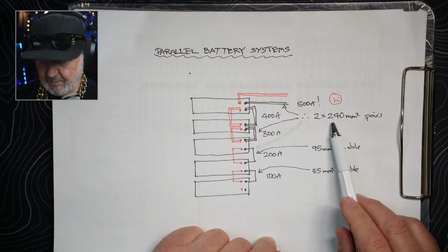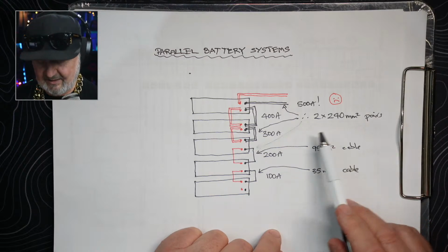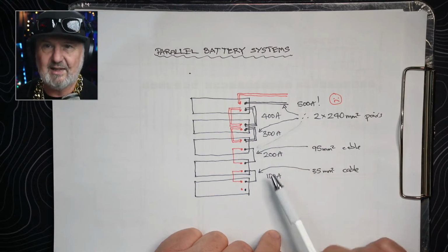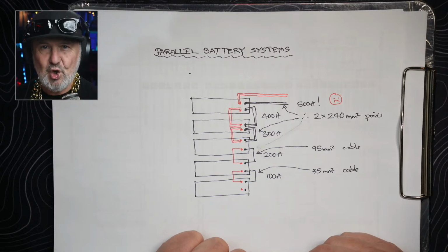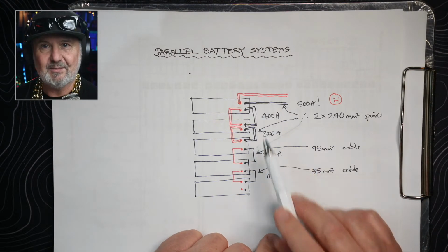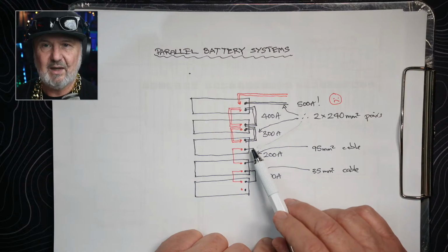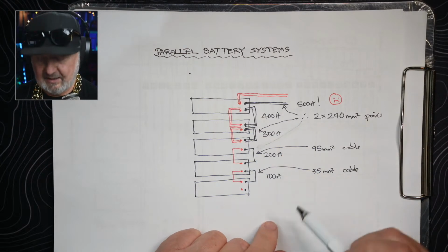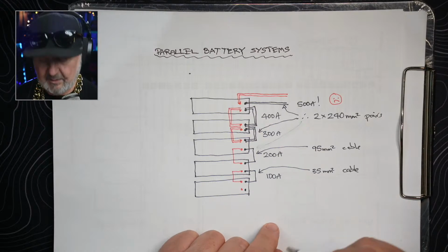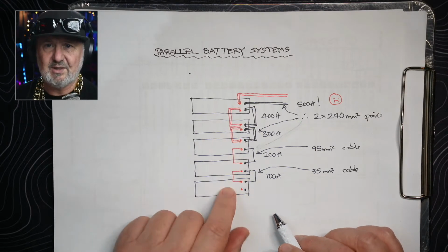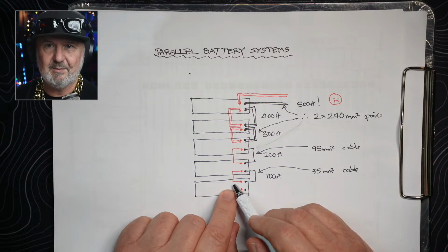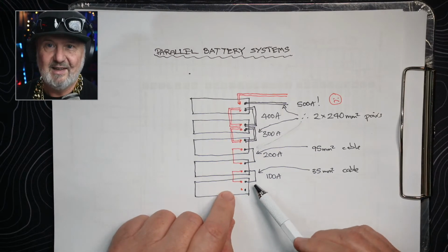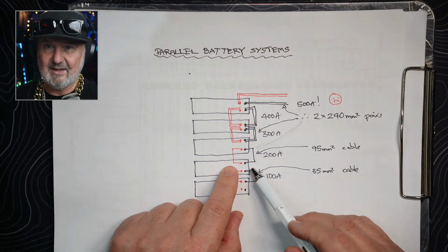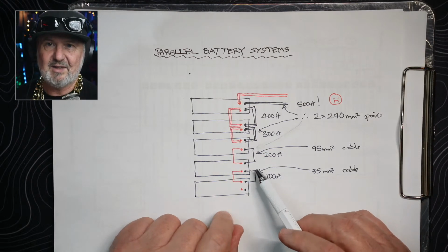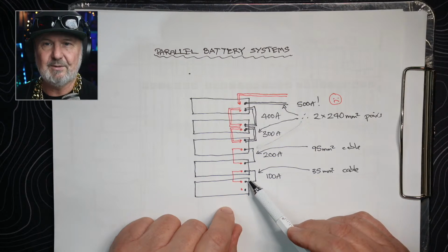On this one, I'm going to have to use pairs of 240s, and the same all through to the last one. So suddenly I've got huge cables coming off this system because the currents are adding together in parallel, and that little link cable is not good enough. Now you might say, hang on, Glenn, there's overcurrent protection on these batteries. That's right, there's a 125 amp circuit breaker in each one of these, or 100 amp even. It still means 100 amps goes in here, and then 100 amps is coming out of each of these. And these terminals are often on the output of that overcurrent protection device, not on the input to it.